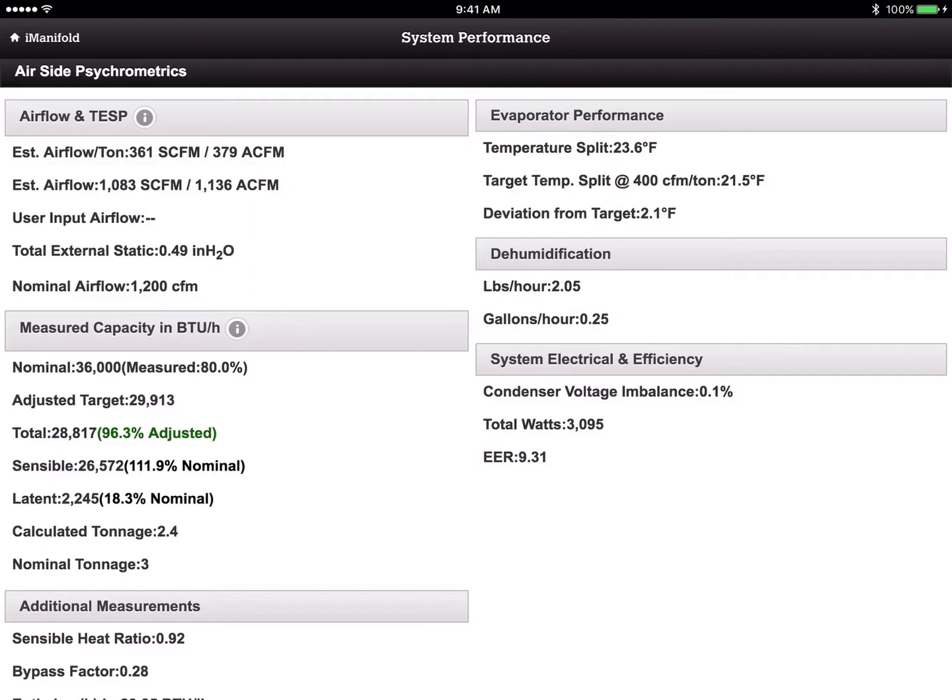So you can see our adjusted target is 29,913 BTUs and we're running about 99% of the adjusted target — things look okay. But let's see how that piece of equipment is actually running, because there are more things we need to take into account to determine if this system is actually operating properly.